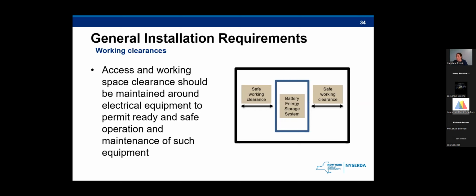So we have the working clearance requirement here. Basically, access and working space shall be provided and maintained about all electrical equipment to permit ready and safe operation and maintenance of such equipment. In accordance with NFPA 70 and the manufacturer's instructions, the clearance for working equipment should be 3 feet, and these clearances should always be unobstructed.